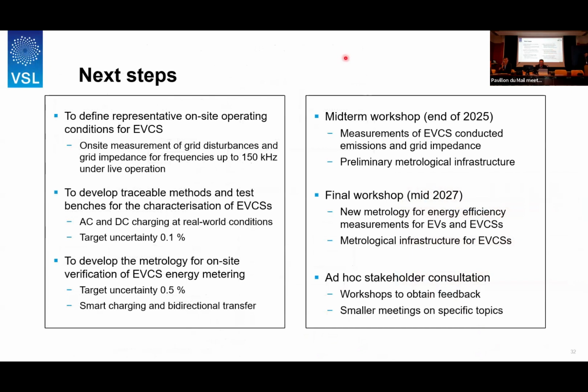Okay, so the next steps are to define the representative on-site operating conditions for EV charging systems, and to develop traceable methods and test benches, as I showed some preliminary ideas already, and also to develop the metrology for on-site verification. I should say that I focus now on the grid disturbances and ignored the grid impedance, but grid impedance will also be one of the things that we need to measure.